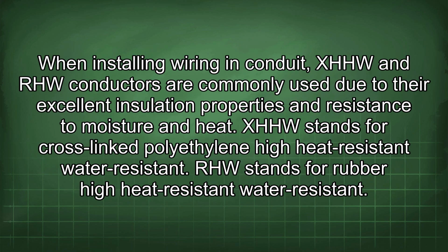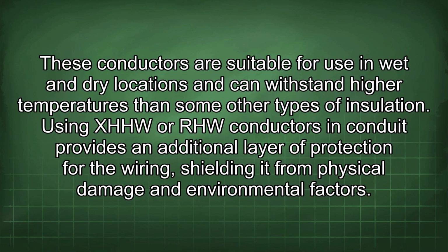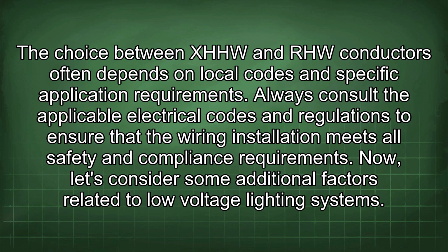When installing wiring in conduit, XHHW and RHW conductors are commonly used due to their excellent insulation properties and resistance to moisture and heat. XHHW stands for cross-linked polyethylene high heat resistant water resistant. RHW stands for rubber high heat resistant water resistant. These conductors are suitable for use in wet and dry locations and can withstand higher temperatures than some other types of insulation. Using XHHW or RHW conductors in conduit provides an additional layer of protection for the wiring, shielding it from physical damage and environmental factors. The choice between XHHW and RHW conductors often depends on local codes and specific application requirements. Always consult the applicable electrical codes and regulations to ensure that the wiring installation meets all safety and compliance requirements.